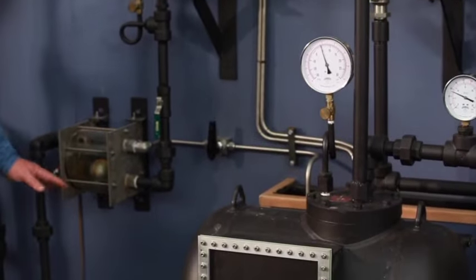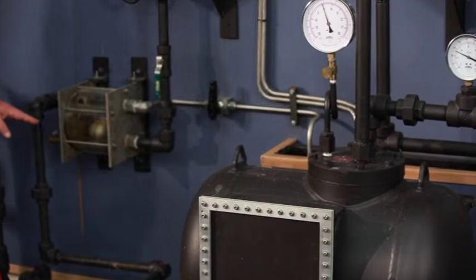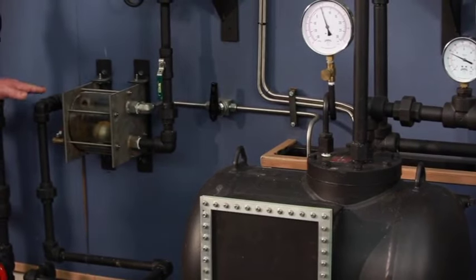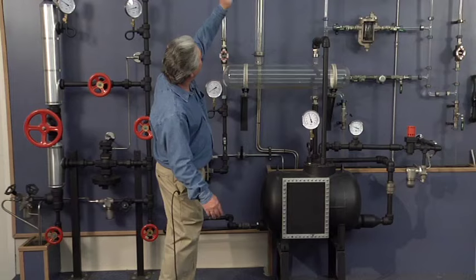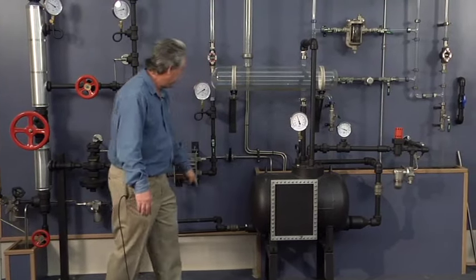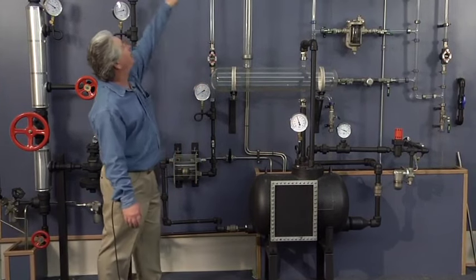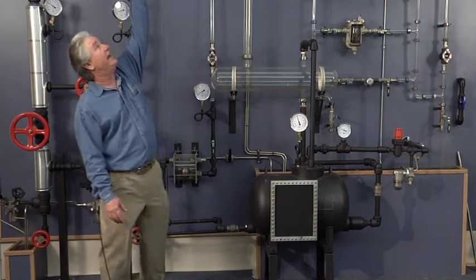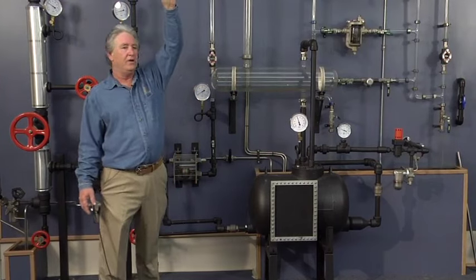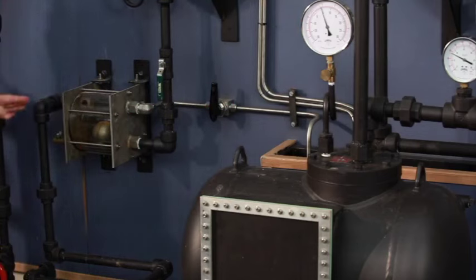We can see that we have a floating thermostatic trap on the downstream side of the pump. This trap is installed so that if the outlet pressure of this exchanger coming through the system exceeds the back pressure that we have trying to lift this condensate and get into the header, we would have steam flowing all the way through this if we had no steam trap.